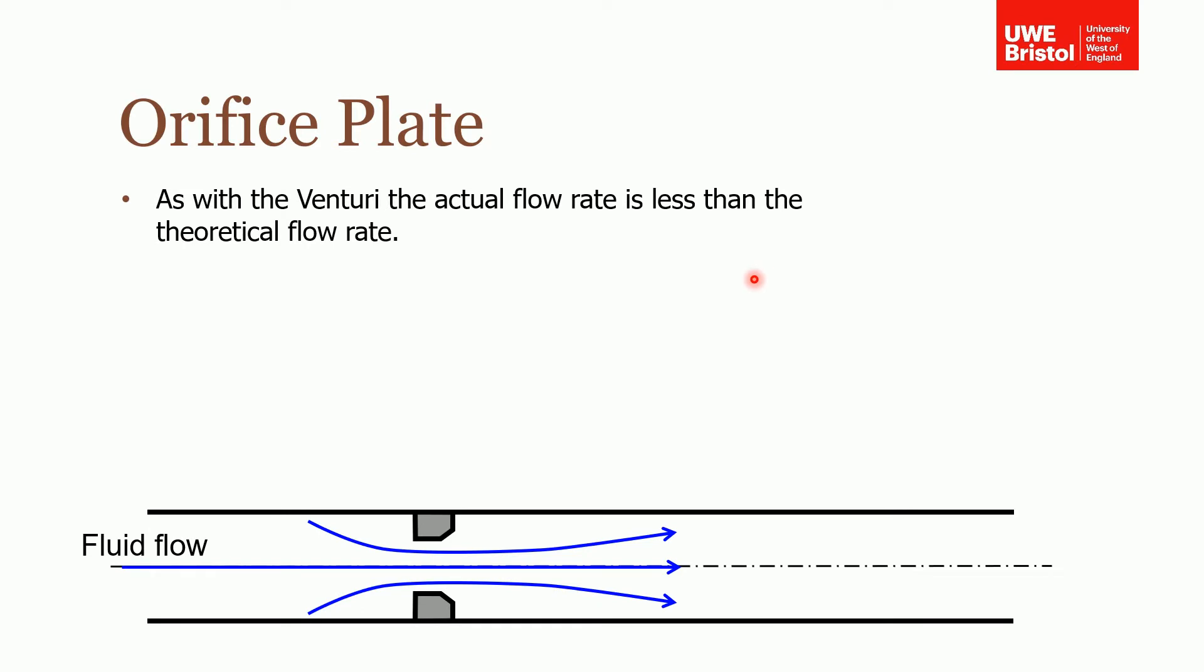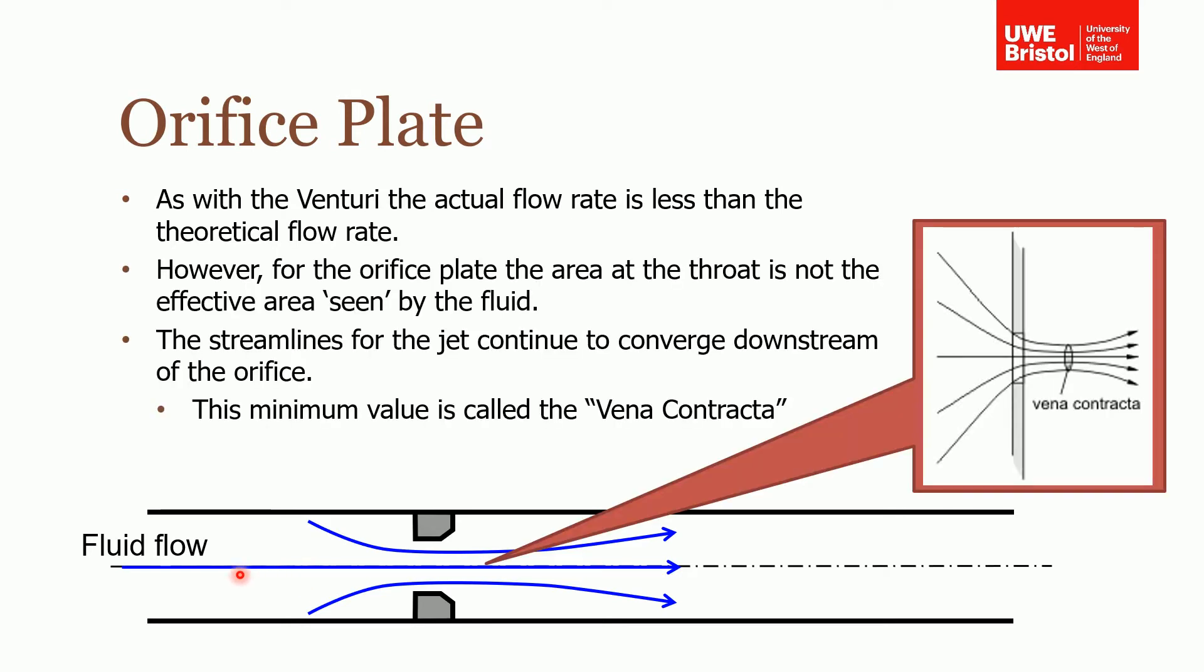However, unlike the Venturi the change in area is slightly different. We said with the Venturi the actual mass flow rate is less than the theoretical flow rate, and that is also true for this orifice plate. But it's even more of a factor for the orifice plate and this is due to the way that the flow flows through that hole.